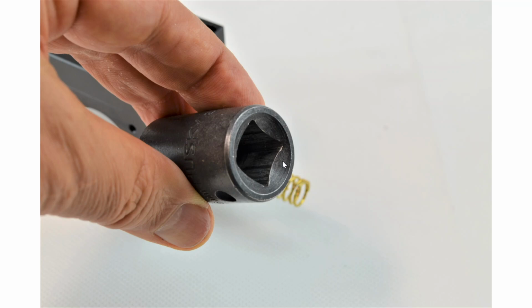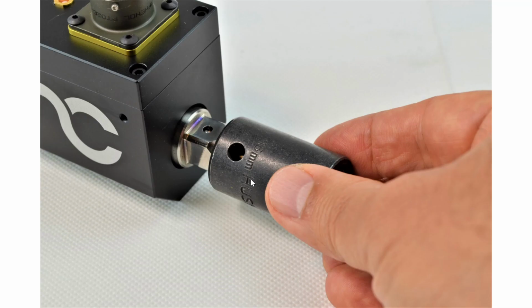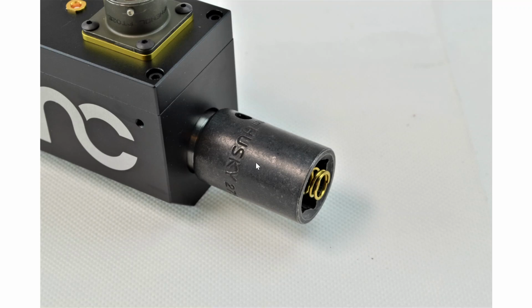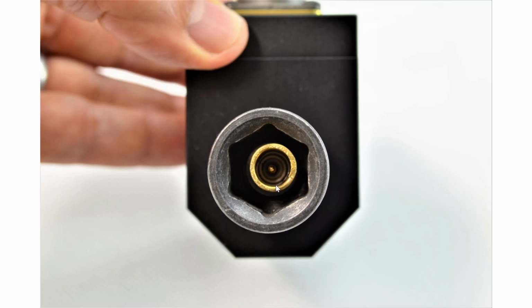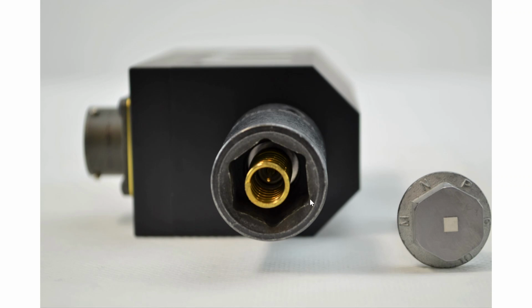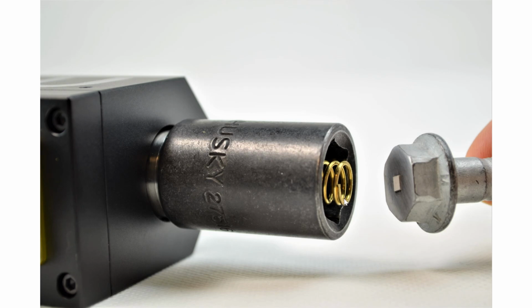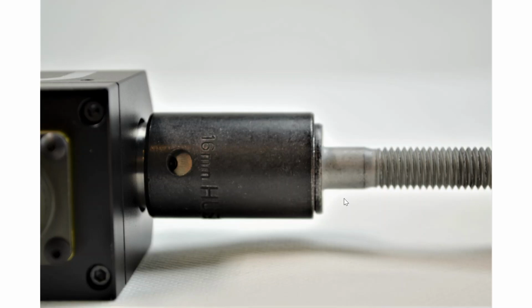We recommend you using impact type sockets because there is no indent inside them. If there's an indent, they might get stuck in the square drive, which has a retaining ring on it. So try to use an impact socket. So slide in, and this is all the way in, so you have it ready for tightening the bolts. This is the front view. This part would touch the bolt, and this part would touch the transducer. Again the same view complete with the socket. So this is ready for tightening. So slide in and ready to go.